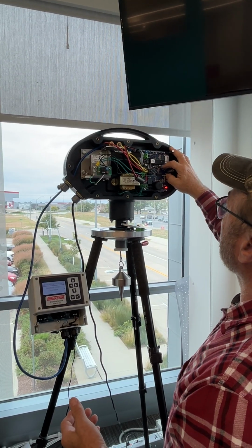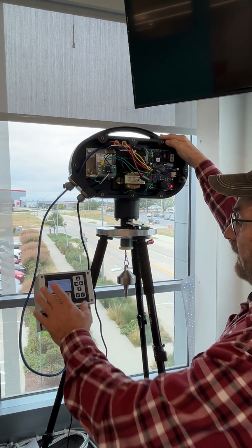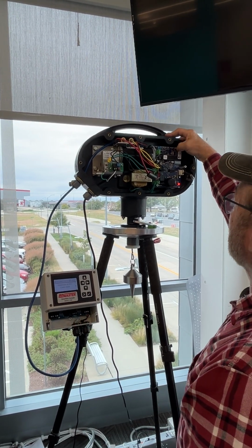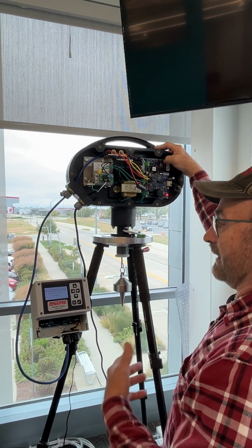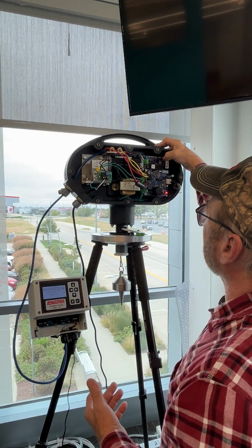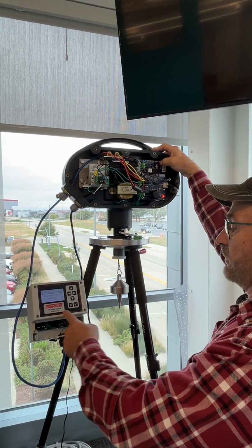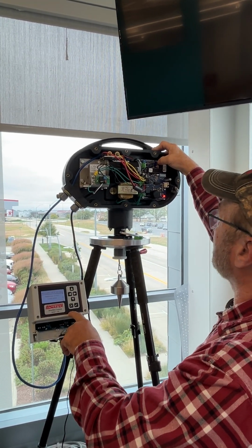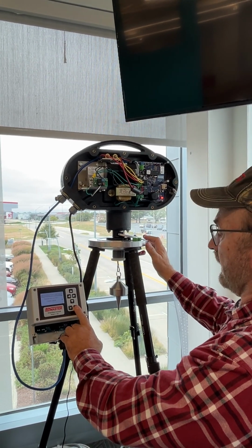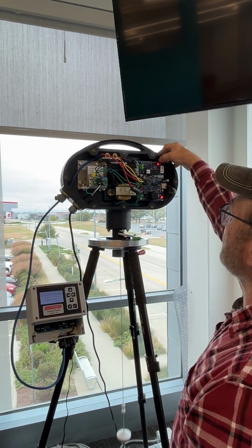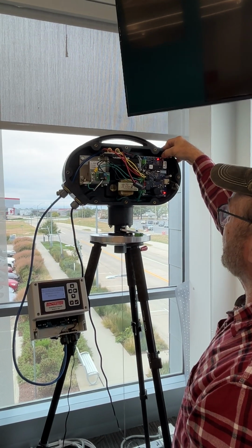and then during the course of a measurement, every second, the console is going to ask the SmartBob what its status is. Are you dropping? Are you retracting? Are you done? And that's why you'll see the busy light flash with the request from the console, and then the transmit light flash giving an answer back to the console. So now I'm back on address 1, so it's alternating back and forth during the measurement.